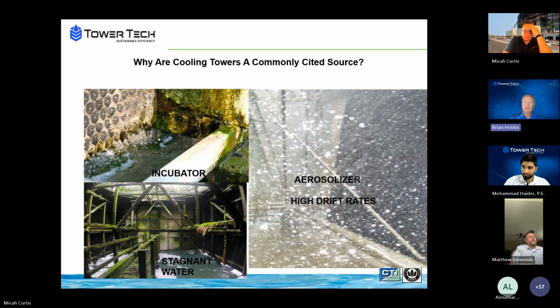And then the aerosolation of the high drift rates is because of the different types of cooling towers, especially the one on the left, the induced draft cross flow, and their drift eliminators do not stop all the water particles that are being produced. I know there's a lot of plume coming out of the top of the tower, but there's still a lot of aerosol water, and that's what people are actually breathing in on these high drift rates. We'll get more into drift rates as we go through, because they're not all the same. There are some controls over this.